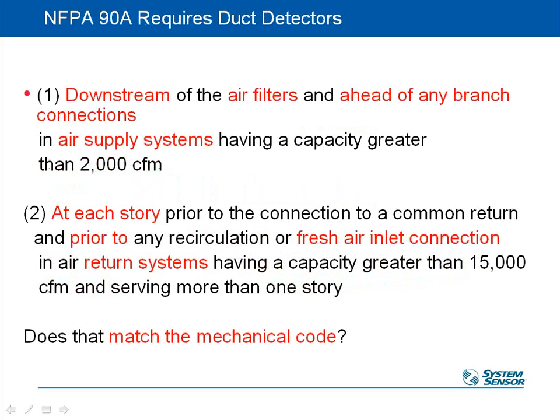You have to put these detectors ahead of any branch takeoffs if you're putting it in the supply air, and after any final filters. So if you're putting it in a rooftop unit and that rooftop unit's going to have some field HEPA filters on the discharge of it, you wouldn't be able to factory install it in the rooftop. You're going to have to go put it discharge downstream of the air filters.